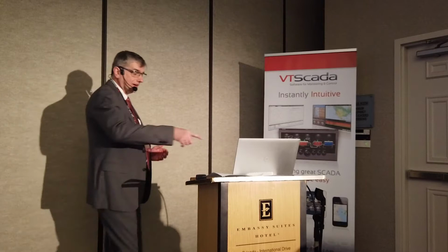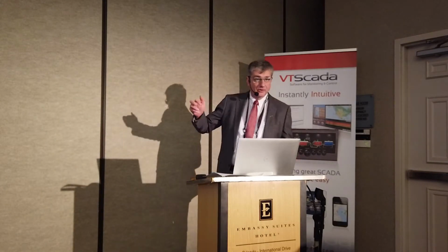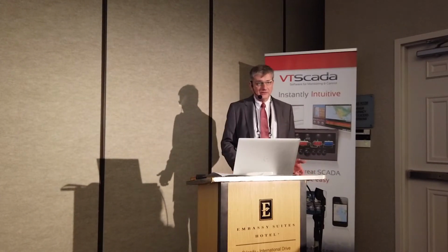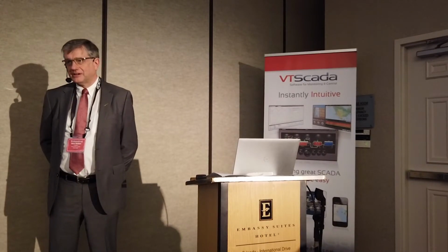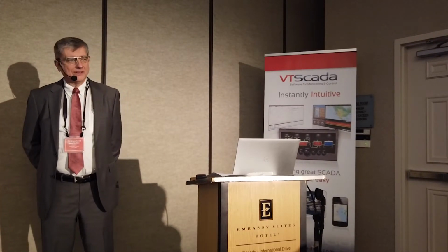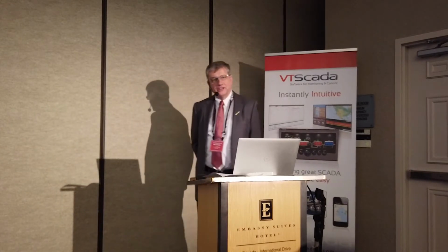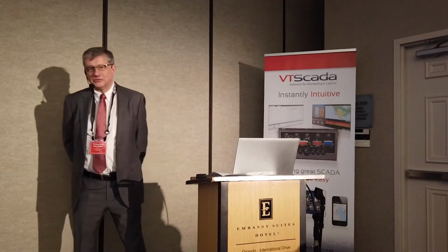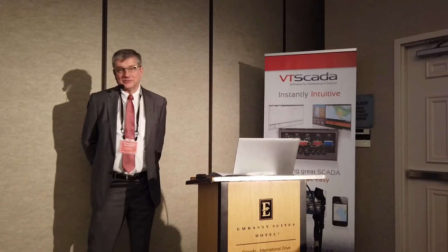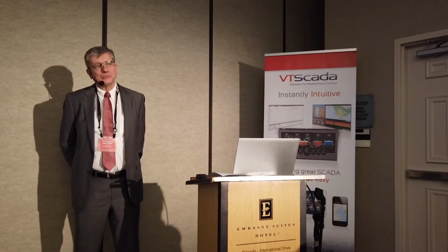But what happens every time that period elapses, it goes to the historian and grabs all that data. I may be running 10,000 records a day on the system. I say I want to look at the average for the last day and I want to update it every second. That's pulling 10,000 records every second and taking the average of them. And you multiply that by 1,000 tags doing that, you'll bring the system to your knees. Do you really need it every second? No, you really need it at a reasonable interval, probably.